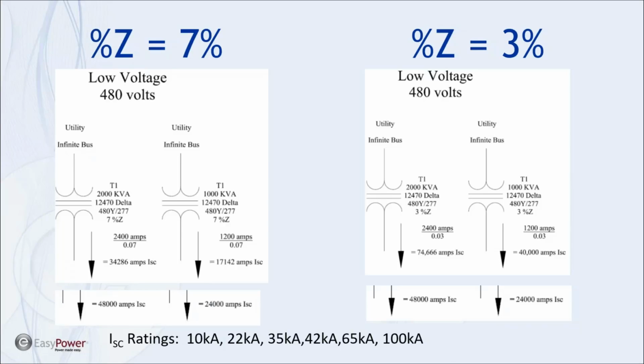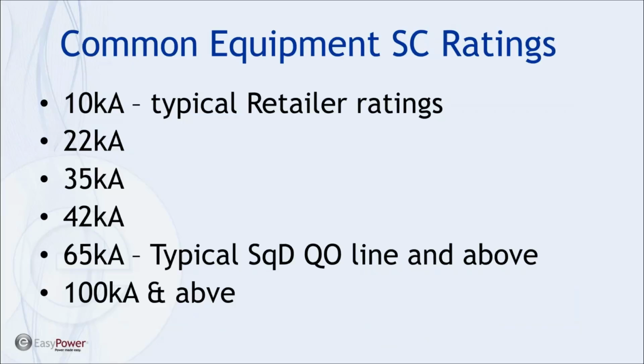Those impedances are not all consistent. It's based on the manufacturer of the transformer. At the place where I worked, what we did is we short-circuited the secondary on our transformers and ran the voltage up until we had rated current flowing. That voltage that we got to divided by the rated voltage is also the per unit impedance of the transformer. So in small pad mounts and pole mounts, they don't test every transformer, but that is where that number comes from. Again, listing of equipment ratings.